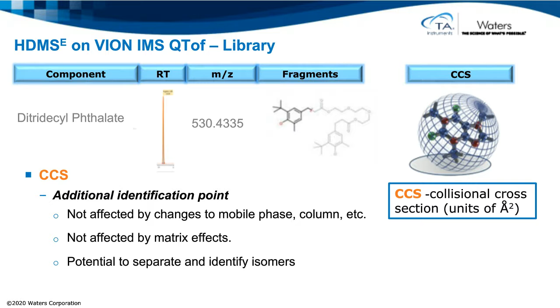So, what are CCS values and how do we obtain them? CCS values, as I said, are found by using ion mobility spectrometry. At Waters, we have the Vion IMS QTOF. And here, in addition to the collision cell that you'd see on the Xevo system, the Vion has an ion mobility drift cell, labeled mobility separation here. Ion mobility spectrometry, IMS, coupled with HRMS, affords an additional separation of ions based on size, shape, and charge as they drift through gas in the mobility cell.